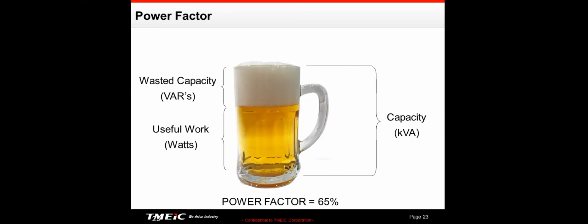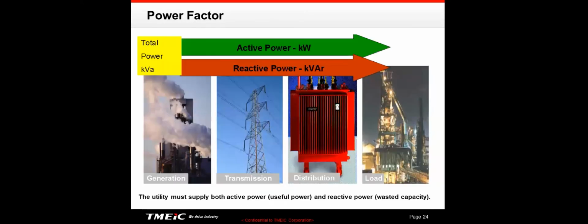So in this case, we take the watts divided by the kVA, and again, that would be 65%. It's pretty much the same analogy. This tells you how much of your current you're actually using to generate real power. And in general, the higher the power factor, the better.